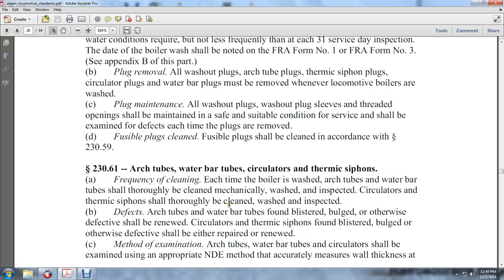Arch tubes and water bar tubes found with blistering, bulging, or other defects shall be renewed. Circulators and thermic siphons with blisters, bulges, or other defects shall be either repaired or renewed. Arch tubes, water tubes, and circulators shall be examined using an appropriate NDE method.